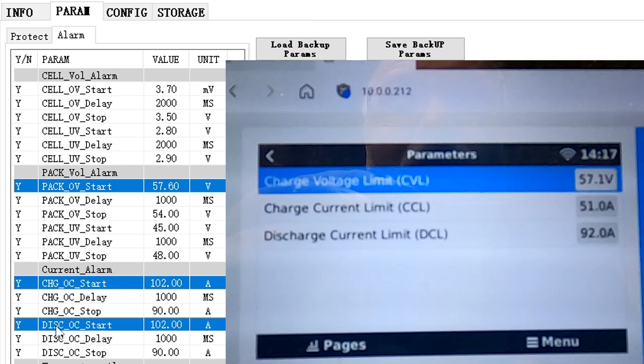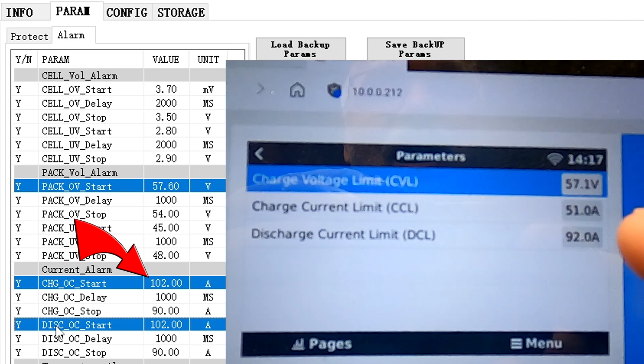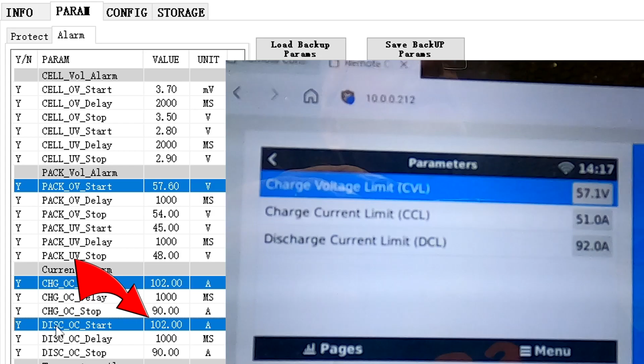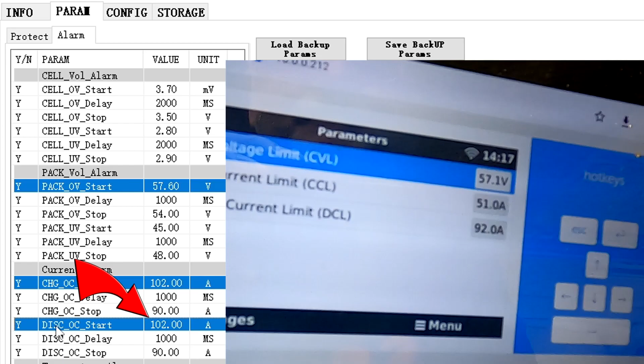The charge current limit, CCL, is at 51 amps, and our charge over current alarm is at 102 - exactly half of what we set in the alarm. The discharge current limit, DCL, in the Victron system sits at 92. Our discharge over current alarm in the BMS is at 102 amps, so 10 amps lower.